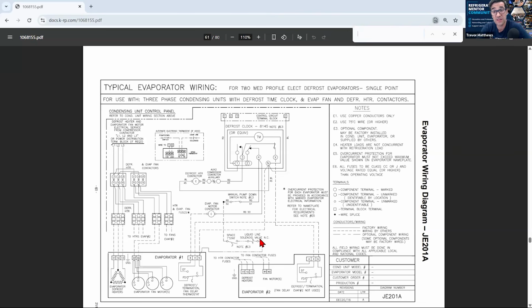So these are some things that are super important. Maybe you're asking, where's the solenoid? Where's the thermostat? Where's the pump down switch? You didn't see it on that other page on the condenser, because that was just the condenser wiring. It wasn't the evaporator wiring. And walking through this step by step, you'll see this one's a 3-phase evaporator versus a single phase one. But walking through that stuff as well, understanding what you're looking at.